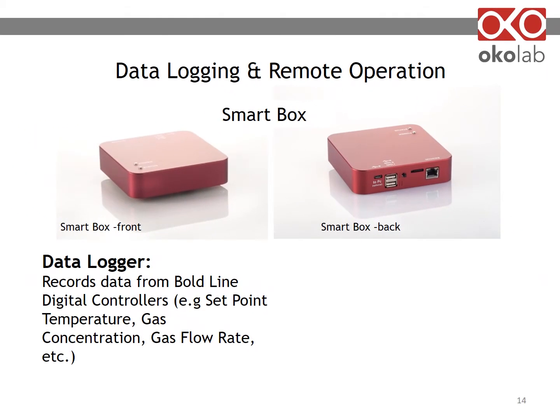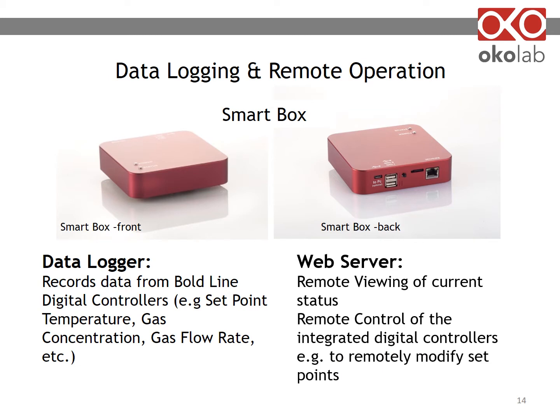Cryo Boldline is compatible with the SmartBox. This is an optional item allowing you to log all the data you see on the touchscreen interface. You can download the parameters as well. You can also use it remotely to view and modify setpoints through a web application.